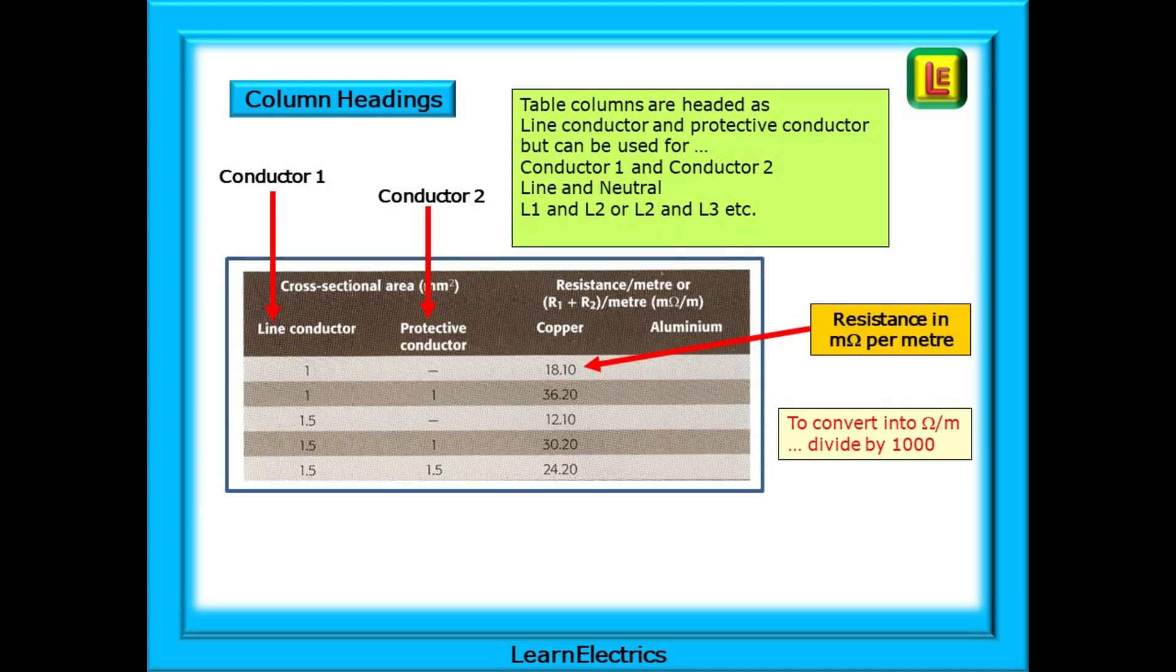Start by looking at the headers for the table. Table columns are headed as line conductor and protective conductor in the table but the headings can be used for conductor 1 and conductor 2 if you are not testing a protective conductor or earth. You can use them for line and neutral or L1 and L2 or L2 and L3 etc in a three-phase system. The resistance values shown in each row of the table is in milli-ohms per meter, thousandths of an ohm per meter length of the conductor.